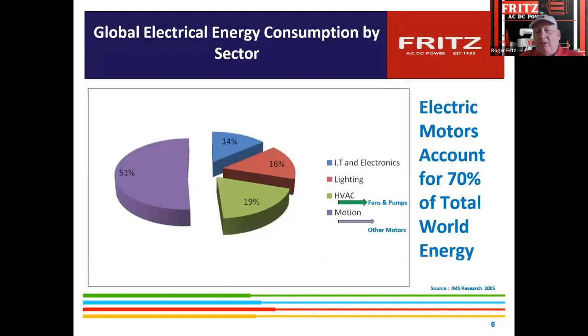So where power is used on motors, about 51% of it goes to motion: conveyors, crushers, big applications, steel mills, those kinds of things. 19% is in the HVAC industry: fans, pumps, compressors. And lighting is about 16% of our power, and 14% is other electronics and light IT equipment, which we can't really do much about. Lighting we can do, but there have been a lot of light bulbs changed in the last several years, and so that's kind of been tapped out for conservation.